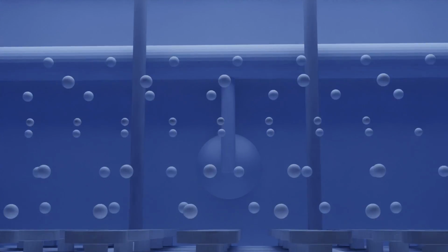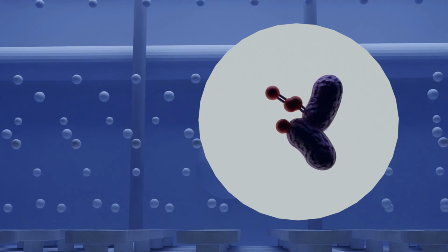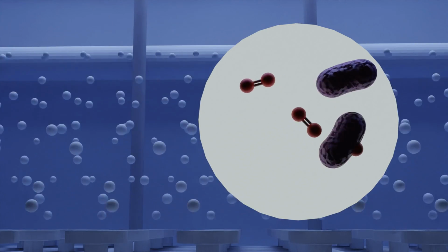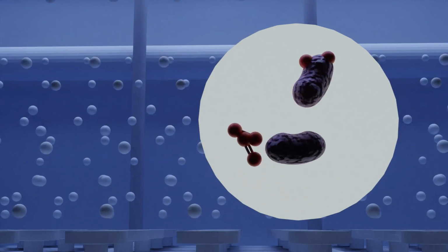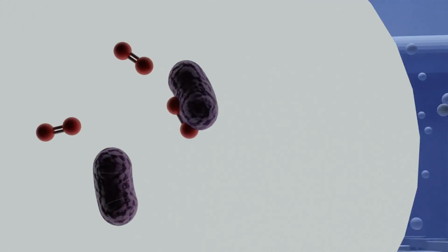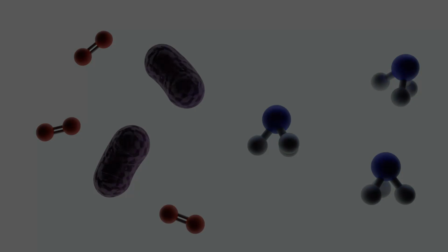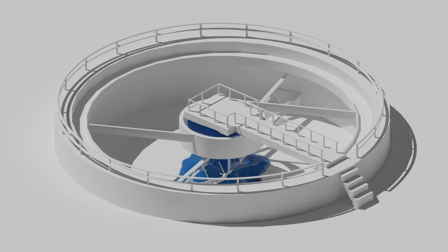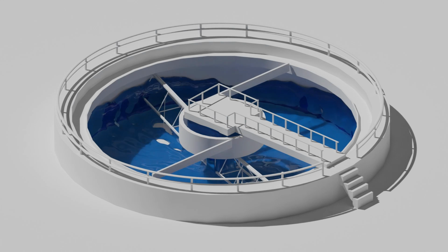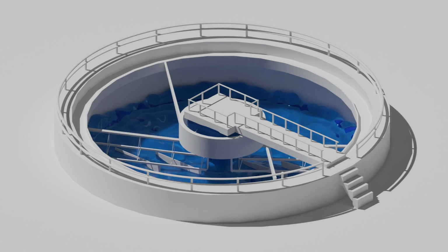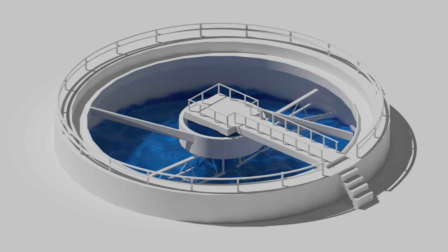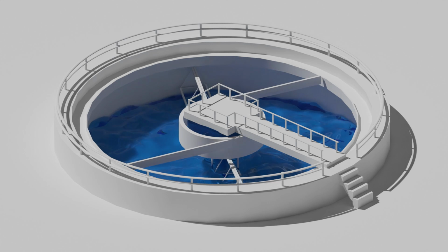Air blowers in the tank create oxygen bubbles in the water. Simultaneously, activated sludge containing microorganisms is mixed in. The combination of microorganisms and oxygen results in aerobic digestion, which allows for the decomposition of harmful substances such as ammonia. After going through the aerobic digestion process, the influent and sludge are pumped into the secondary clarifiers to allow for the algae and other large particles to settle one last time.